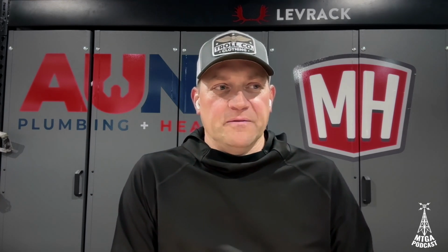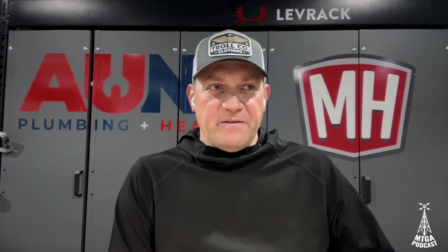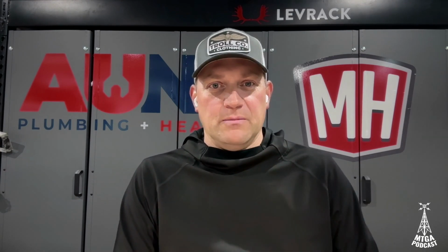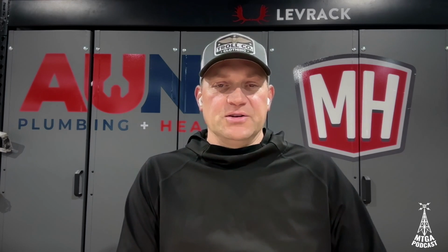If you think about that, what advantages do we have with a big delta T? Well, if we've got moderate outdoor temperatures, we've got heat available. If I've got a nice cold return temp coming into that outdoor monoblock, I can dump a ton of heat pretty easily into that water or glycol solution and return it at a higher temperature without as much work. That's the basis of a heat pump water heater: using the compressor and refrigerant transfer, we're doing mechanical advantage to compress heat into a glycol solution.